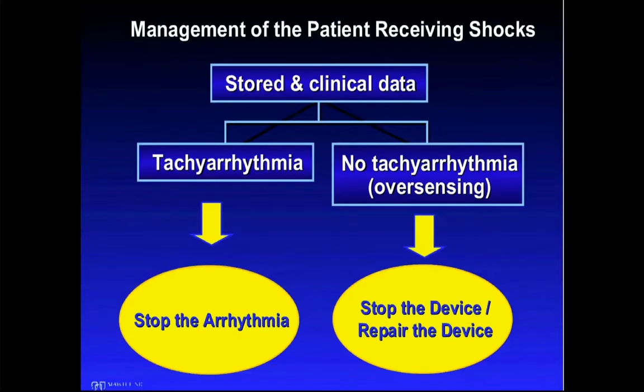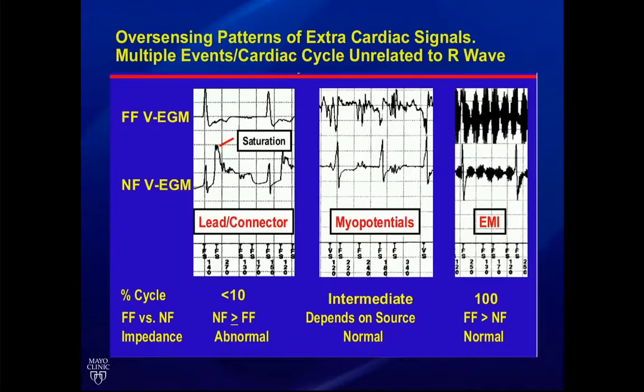When you have a patient you're called about in the emergency room having shocks, the main thought process and reason for interrogating the device is you have to figure out what you need to do. Do you have to stop the arrhythmia, or do you need to stop the device? Is it appropriate or is it inappropriate? The way interrogating the device works is you look for something like this.